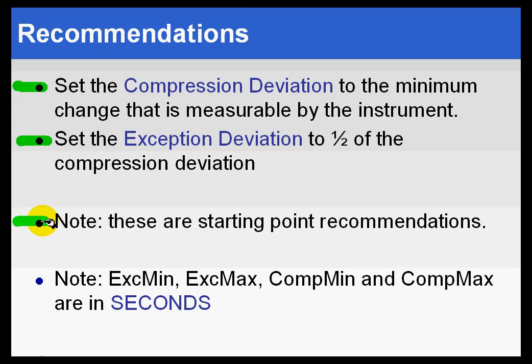However, they are the starting points. One of the things I would suggest you do is set up, say, 5% of your tags and make it a good representative — 10%. Make some of them network traffic monitors, some of them temperatures, some of them pressures, some of them levels, flows, whatever it is you're measuring. Just a variety. And then watch how those collect data. Of course, not everybody has the time to set up 5% of your tags, watch the data, and then make adjustments. But it is the best way to tune the system.